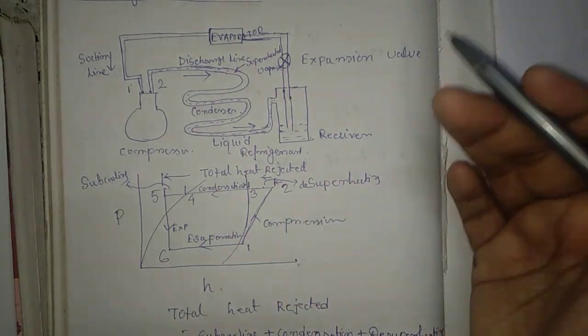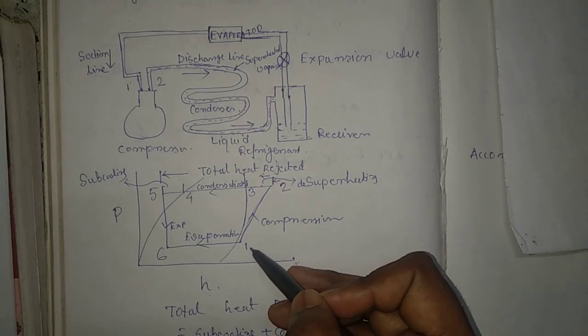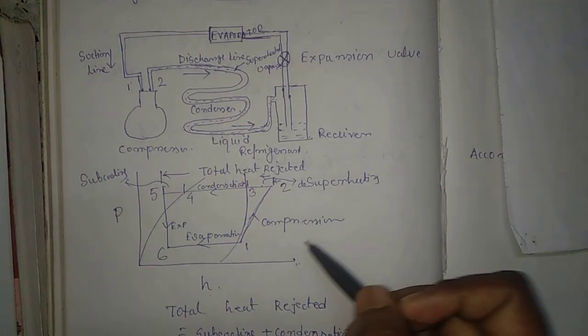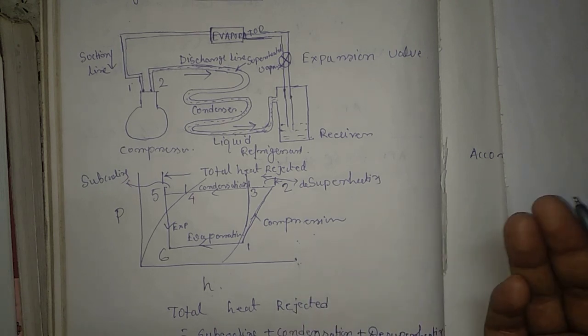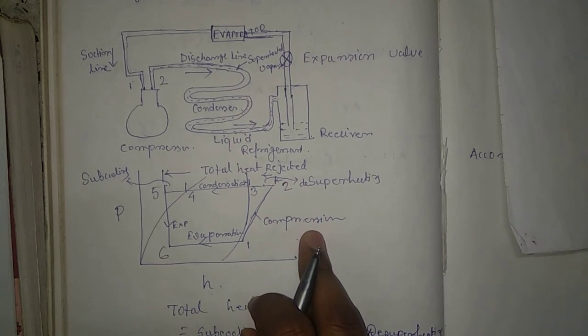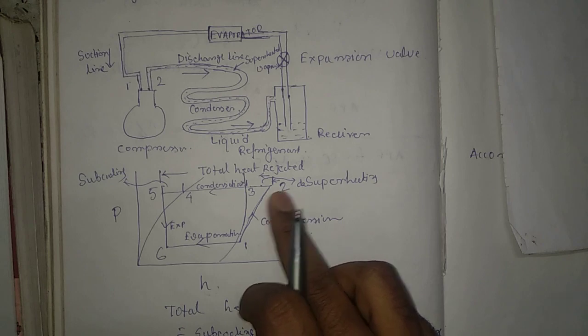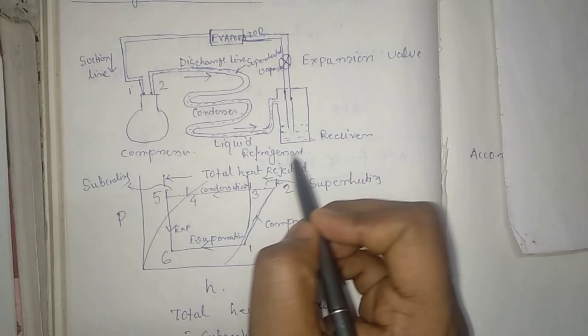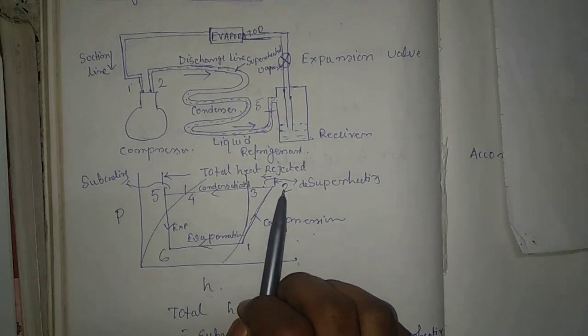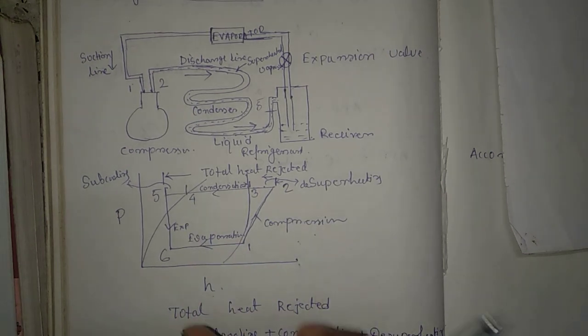The main function of the condenser is to reject heat. In the pH diagram, process one to two represents the compression process — a reversible adiabatic, or isentropic, process. From two to five is the total heat rejection process, which occurs within the condenser. This total heat rejection process covers processes two to three, three to four, and four to five.